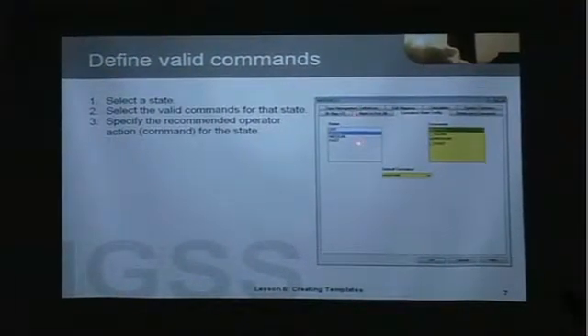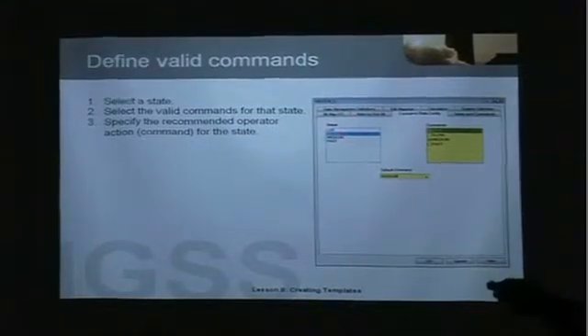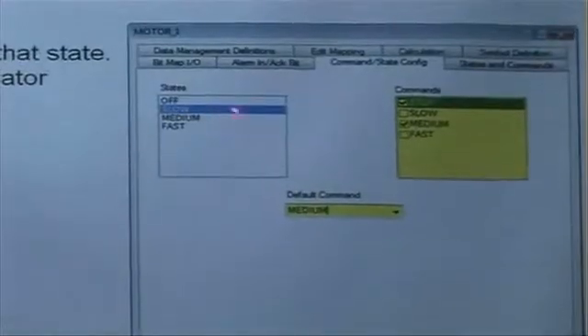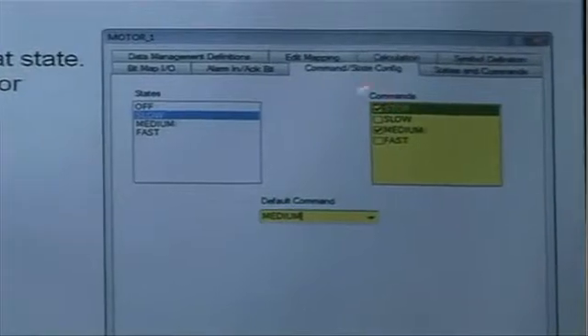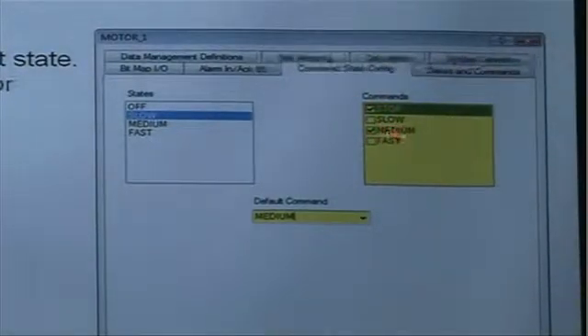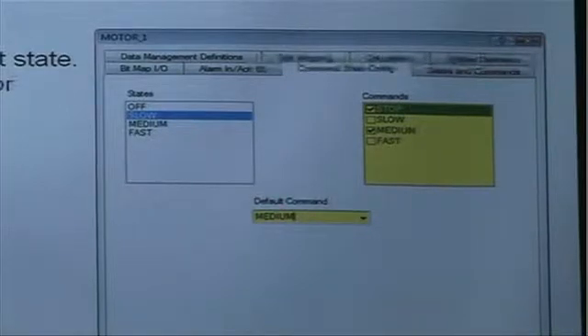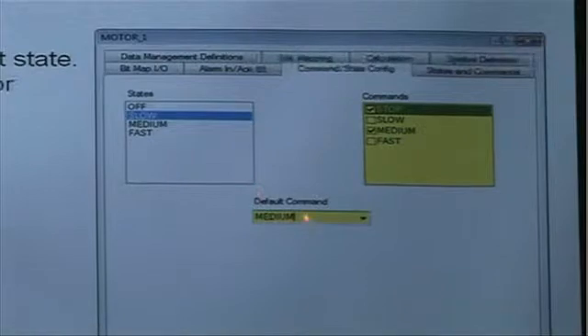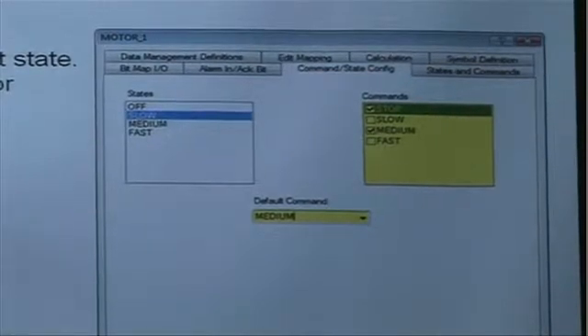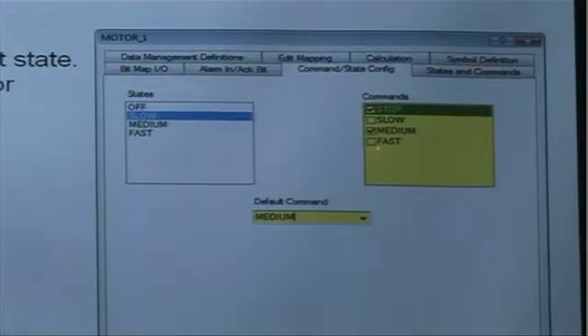When we define the valid commands for a state, we first select the state. Here I have selected the slow state. When the motor is in the slow state, I have defined that the operator can only stop the motor or set it to medium speed. I can also give a recommended operator action — that's what we call the default command. We can indicate to the operator that the medium command is the recommended command; this will be bold in the command menu in supervise. Defining valid commands prevents the operator from sending a wrong command.